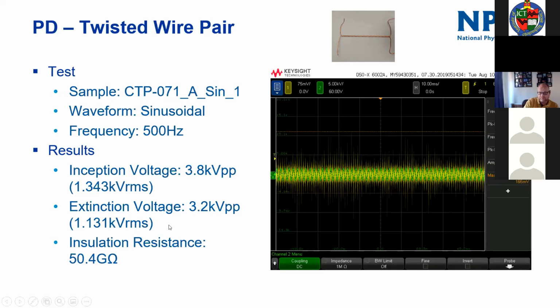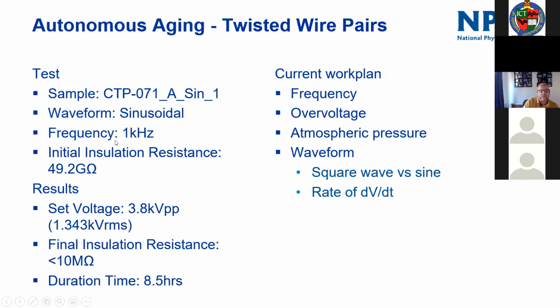Once you set the PD up, it actually continues as the voltage drops. In this particular sample, the extinction voltage, that's the voltage at which PD stopped being measurable, was down at 3.2 kilovolts peak to peak. At this point, this sample has an insulation resistance of about 50 gigaohms. We then aged that sample, in this case with a sinusoidal waveform at 1 kilohertz. We set the voltage to 3.8 kilovolts peak to peak, which is slightly above the inception voltage, just so we got continuous PD discharge. The insulation on those twisted wire pairs broke down to less than 10 megaohms in about 8.5 hours at 1000 hertz. And we're continuing this work at the moment.